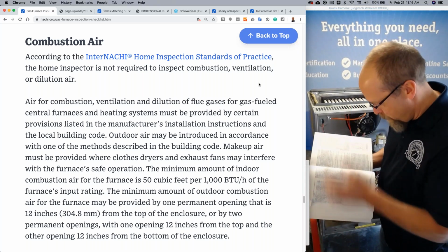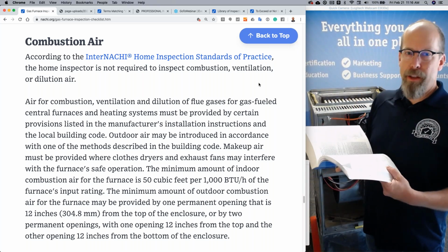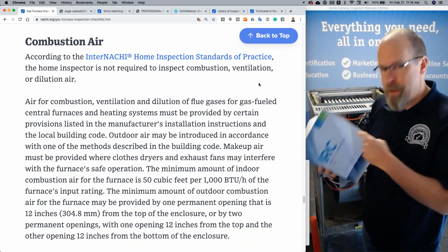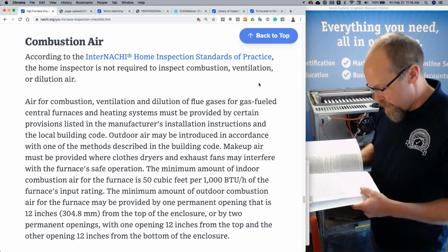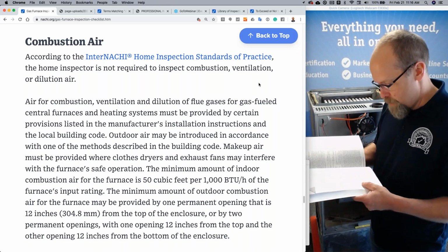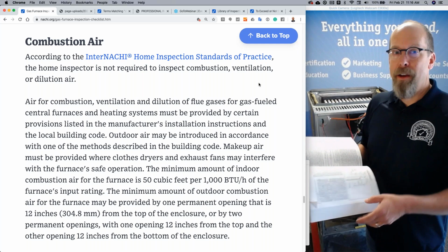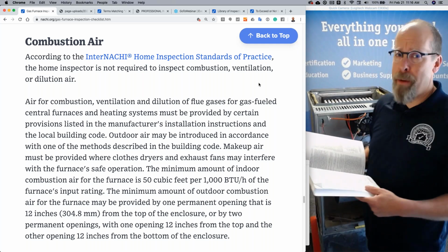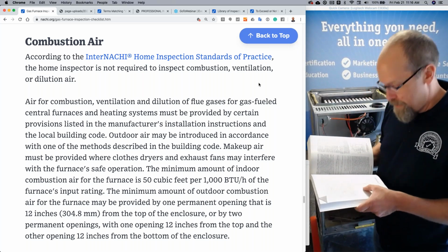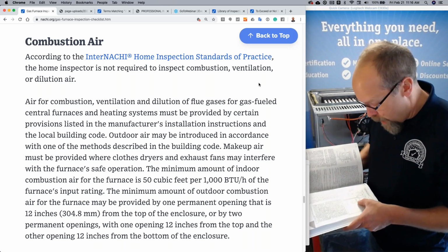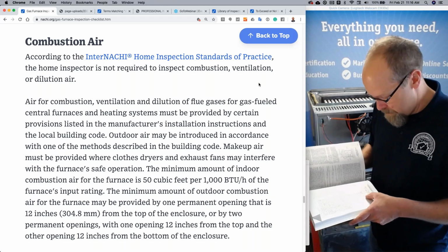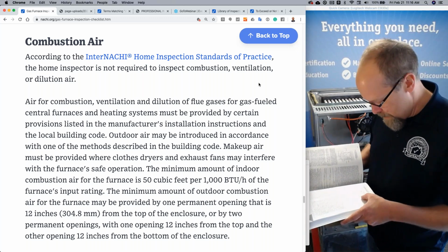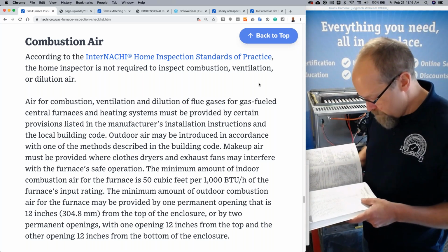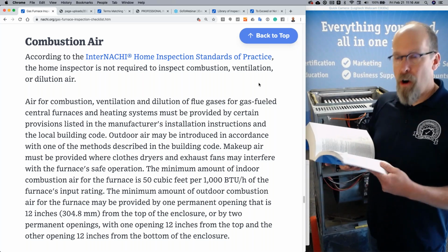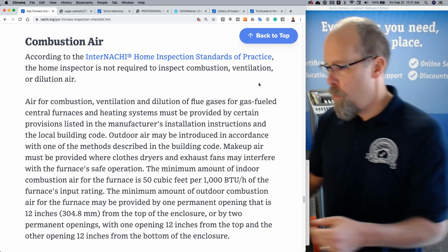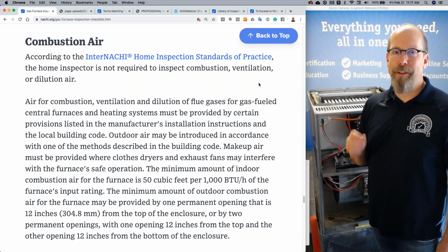And in the code book, you won't find a lot of illustrations in the code book itself, but I found that the code and commentary versions are really helpful because of these commentary figures in section G2407.4. And there's a lot of things that compete with a gas-fired furnace like this one that needs combustion air from inside the house. I mean, there's a bath exhaust fan that could run 80 cubic feet per minute, a range hood in the kitchen that could run 100 cubic feet per minute, a fireplace, hundreds of cubic feet per minute. Clothes dryer, 150 cubic feet per minute. A boiler, a water heater, another bath exhaust fan. I mean, they're all depleting combustion air away from something that needs it in order to have safe operation.